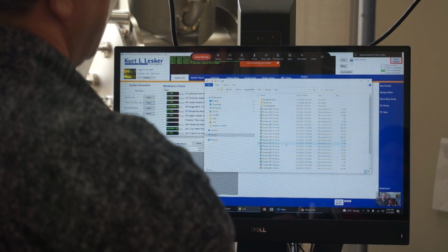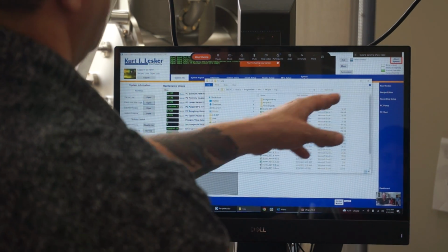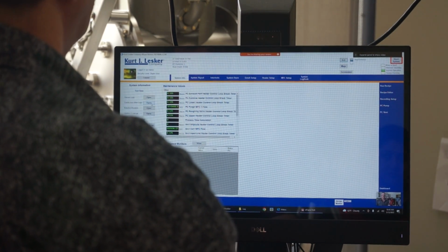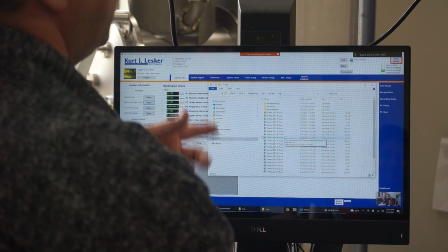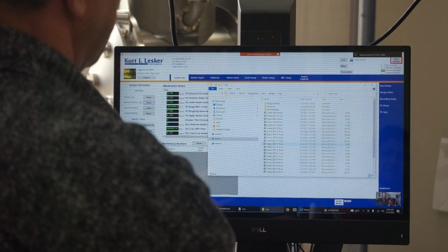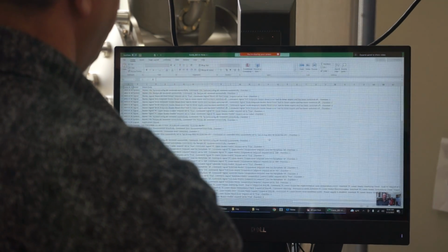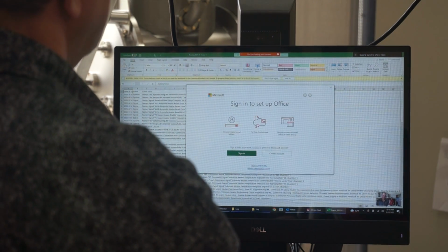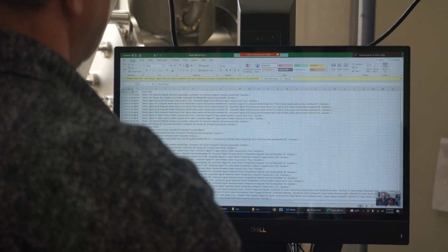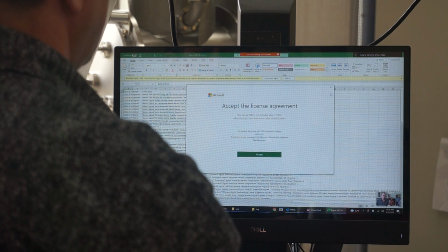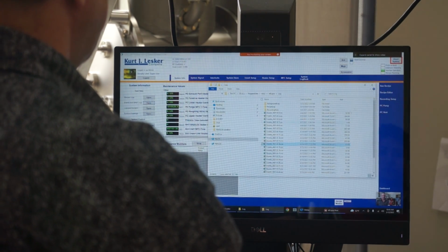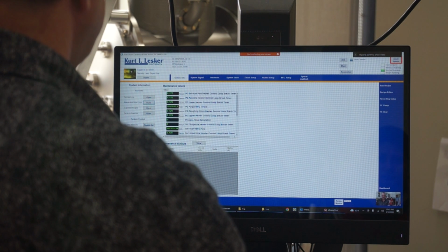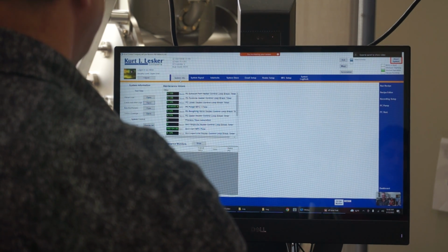So if somebody did something and they went up and cleared acknowledge, and said, I didn't do nothing. No. This gets recorded all the time. You can come into the events, open it up, and figure out what happened through here. That gets recorded and backed up every 24 hours. Under maintenance, system info.